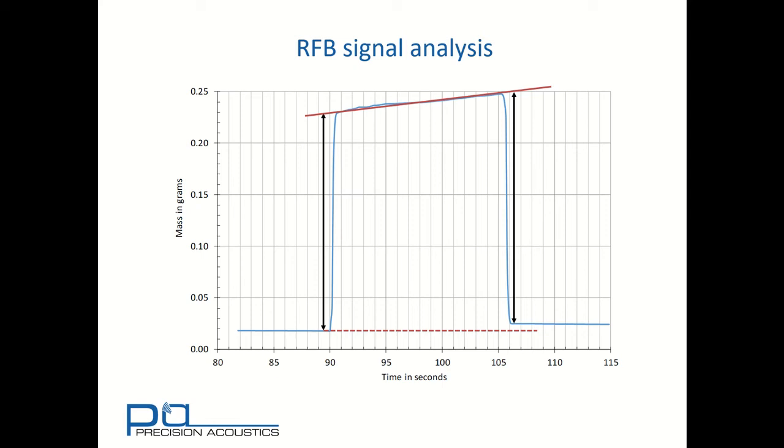By looking at four cycles, we have four independent measurements at ongoing transitions, and four independent measurements at off-going transitions, giving us eight measurements in total, and giving us a good ability for statistical analysis and formation of mean and standard deviation. This all contributes to a very low level of measurement uncertainty.